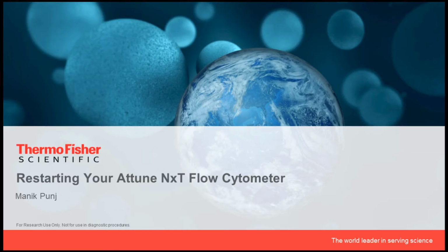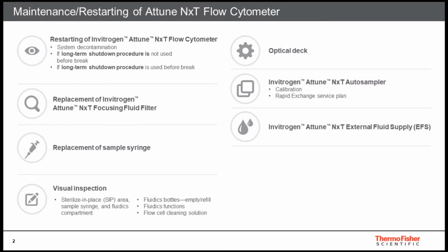I am a field application specialist with Thermo Fisher Scientific, and in this presentation, we will go through Attune NxT Flow Cytometer's maintenance procedures, especially after the instrument has not been used for some time. We will begin by going over some of the fluidic maintenance scripts that will be used in the restarting procedure. Next, we will go over the restarting procedure that will involve whether or not the system was put in long-term storage before shutdown. Lastly, we will finish the presentation with some general maintenance that will ensure interruption-free operation of the Attune NxT Flow Cytometer.